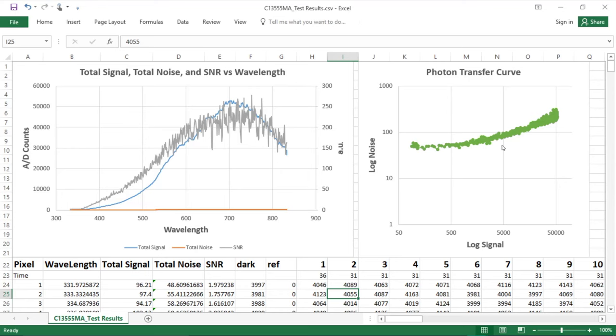Another plot we can put together is noise versus signal. Now if we take the log of each axis, we'll get our photon transfer curve. At the lower light level range, we'll see that measurements are dark noise limited. However, as signal levels increase, the system becomes more shot noise limited rather than dark noise limited. This plot shows the importance of knowing your light levels and how it relates to overcoming the spectrometer noise floor and how it relates to obtaining shot noise limited regime operation.